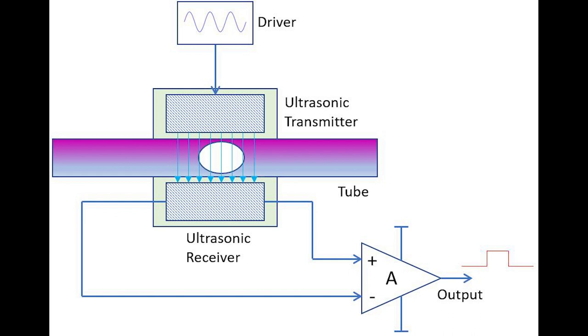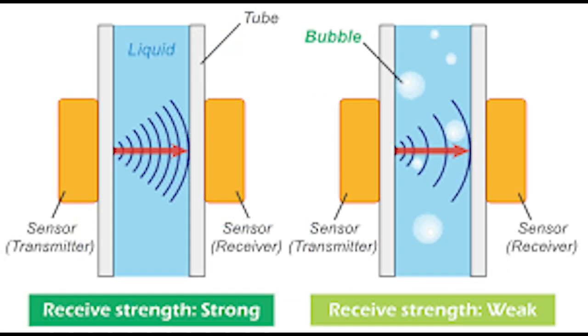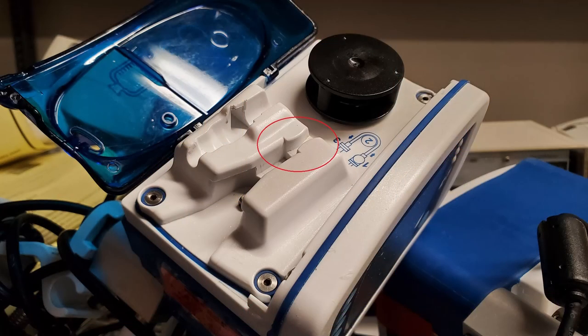In the absence of that medium, the signal stops and the integrated computer will register the event. Ultrasonic sensors can be used to detect air bubbles traveling up infusion lines to a patient, but they can also detect when consumables like infused products are empty, when medical providers load new infusion sets.